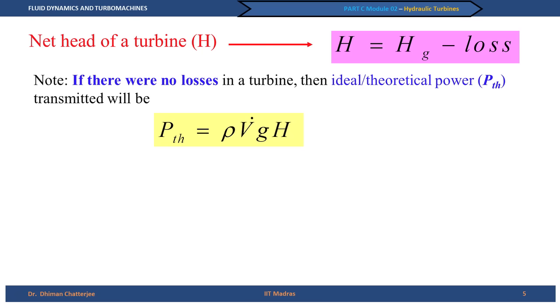No machine can be 100% efficient, as we discussed in thermodynamics. Different losses are present: hydraulic losses (including friction losses and shock or incidence loss), leakage loss, disk friction loss, and return flow loss. Return flow loss in turbines is not very significant, and disk friction loss is generally applicable for turbines except for the Pelton turbine which moves in air.